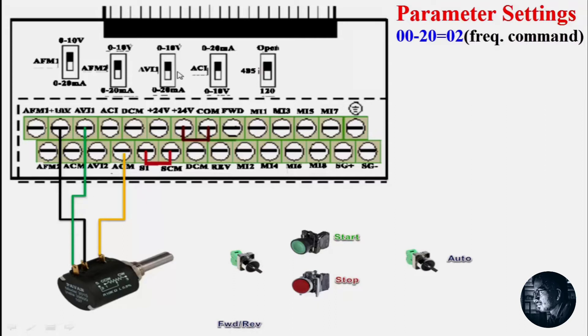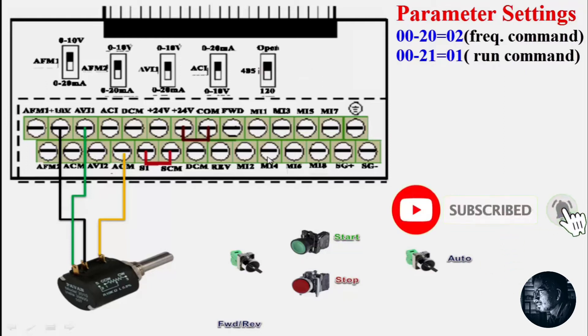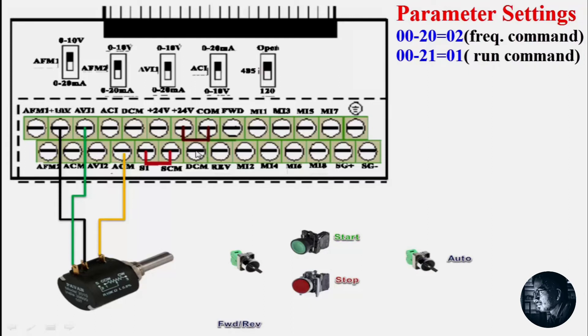For analog input selection we have a DIP switch. For control terminal wiring: Delta drives are by default in NPN mode, that is 0V command. In this mode, DCM is the digital command reference, and all pushbutton and selector switch commands are given to DCM.